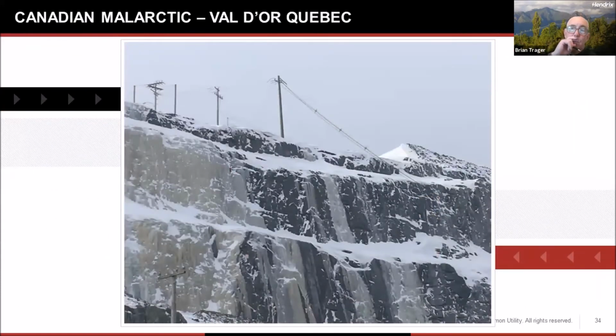So we had a project whereby we were able to bring spacer cable down to that portable substation on a sled, as well as have the ability to move that line when that sled moves, because there's only so much blasting you're going to do and pick up all the raw material with the shovel before you have to move that blasting location.